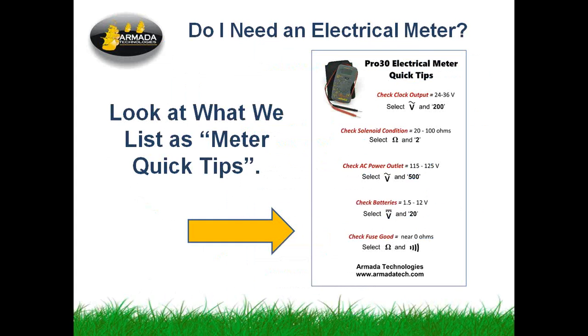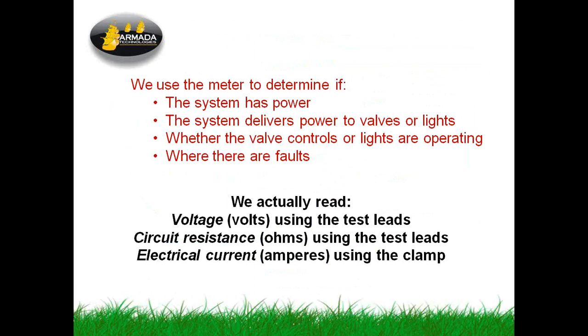checking the voltage at the output of the clock, checking the resistance of a solenoid to find out if it's good, checking your AC power outlet to make sure the voltage is there for driving the controller and clock, even checking fuses. I usually say if a fuse looks like it's good, don't trust it. Always ohm it out, and a simple electrical multimeter will allow you to check to make sure the fuse is actually 0 ohms and didn't blow in a way that you can't see, which sometimes happens. So in the end, we're using an electrical meter to tell us some real physical world stuff. In some ways, we don't even care whether it's 24 volts or 12 volts or something else.